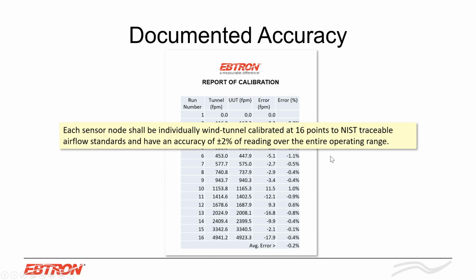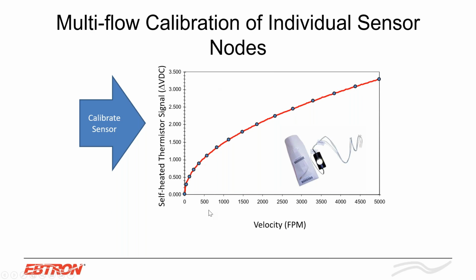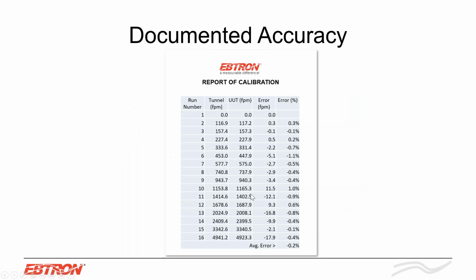And this is just a specification item that if engineers do like the EBTRON product line, they can put in their specification. Again, we're also a percent reading device. So over this entire operating range, we're going to be able to read accurately. Once it's installed in ducts, we say plus or minus 3% of reading. Doesn't matter if you're at 50 feet per minute or 5,000 feet per minute, we're plus or minus 3%.